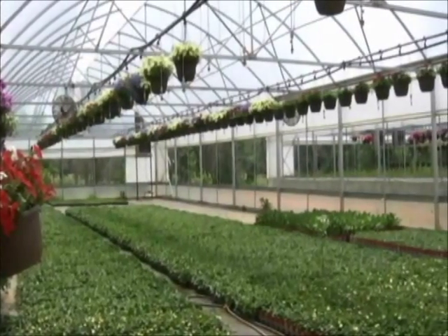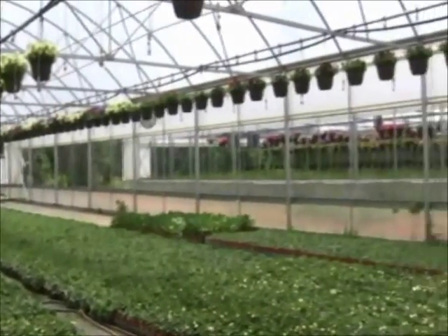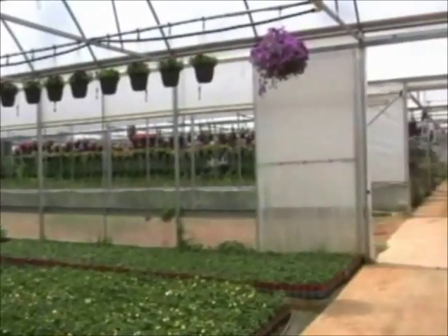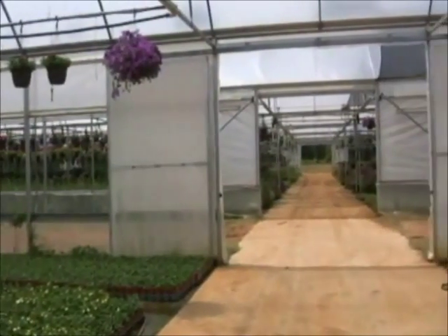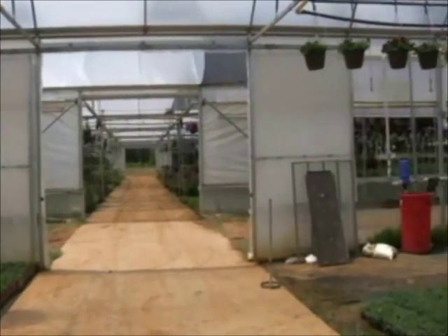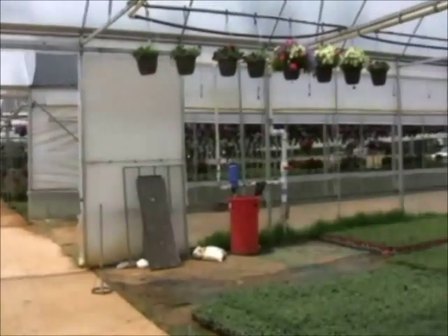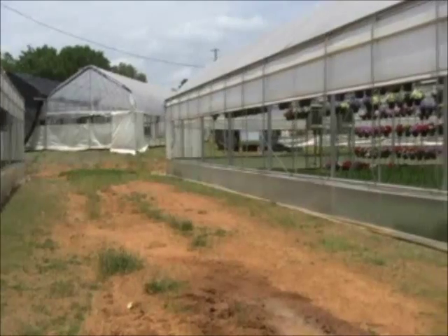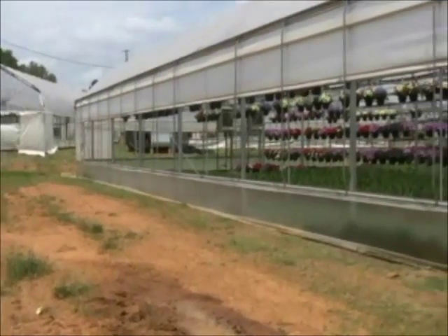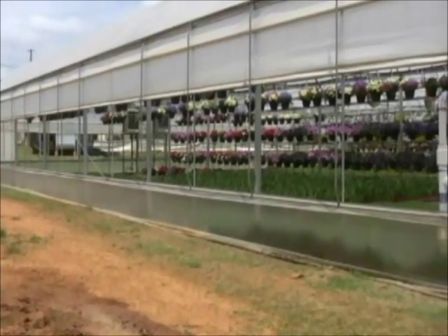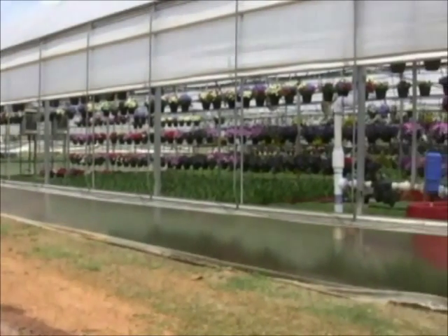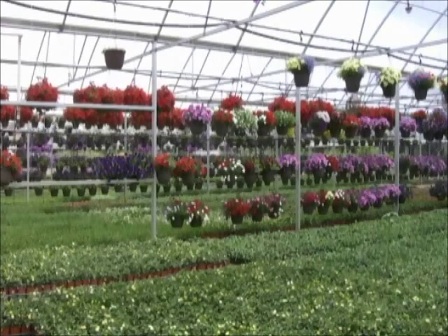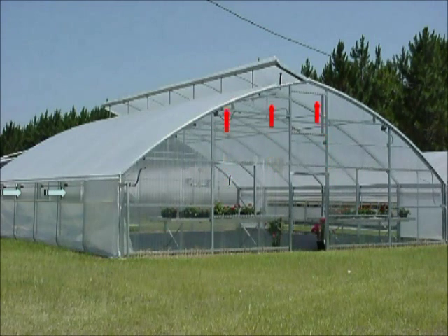Greenhouse ventilation involves removing air from the inside of the greenhouse and replacing it with outside air. Natural ventilation does this by taking advantage of the forces of wind and temperature in such a way as to create a natural air exchange process. This can involve using sidewall and endwall vents alone, and in some situations this approach can provide adequate ventilation. However, the best performing systems include a combination of roof and wall vents that have been sized according to sound ventilation principles.